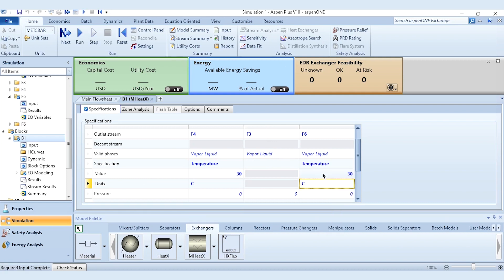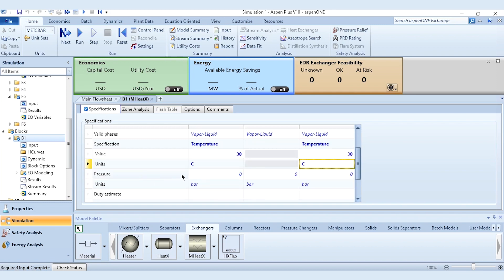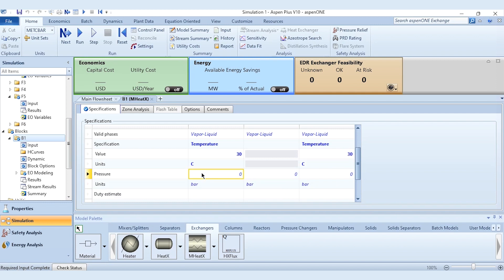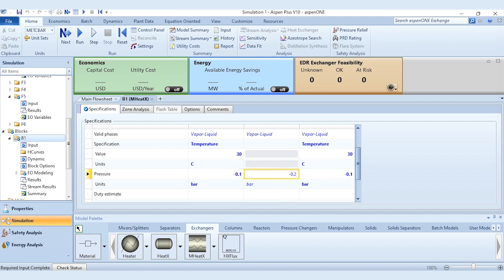Make sure to click on the hot side specification, not the cold side. With the 30°C temperature entered, the required input is now complete. Scroll down to enter the pressure drops: 0.1 bar for both hot sides and 0.2 bar for the cold side. Now run the simulation.